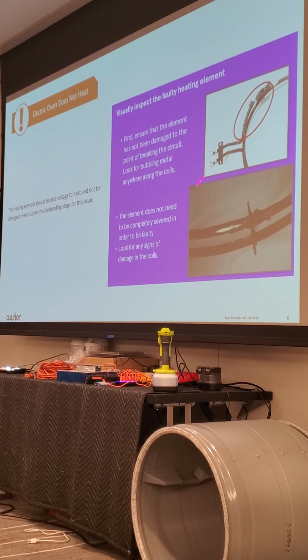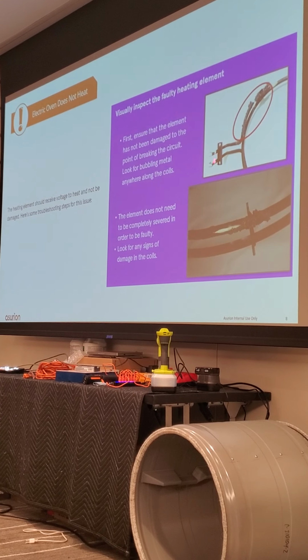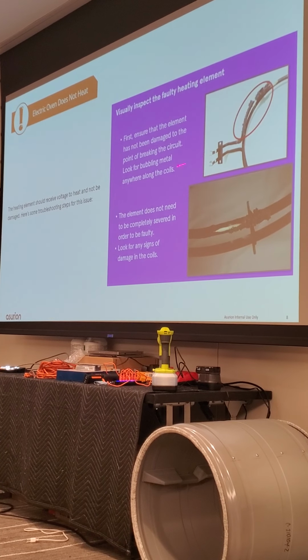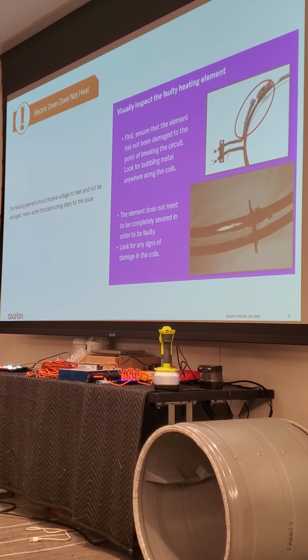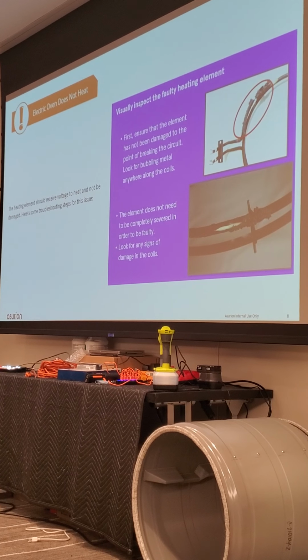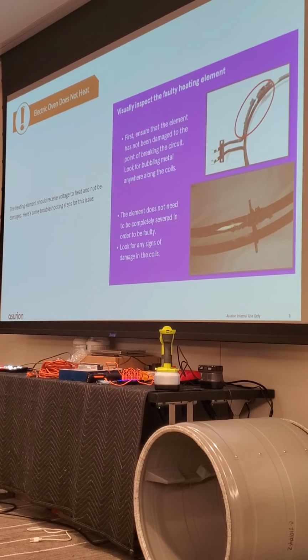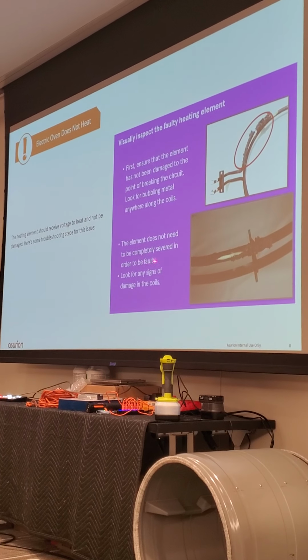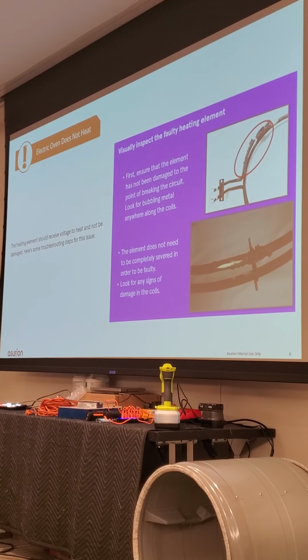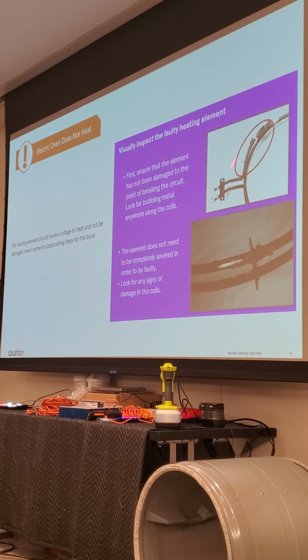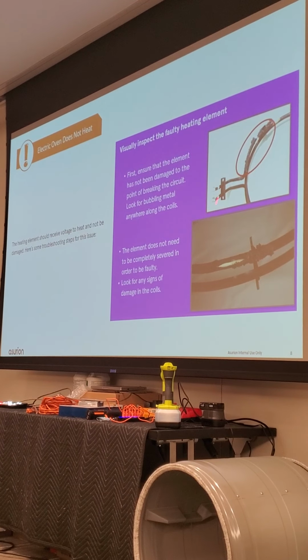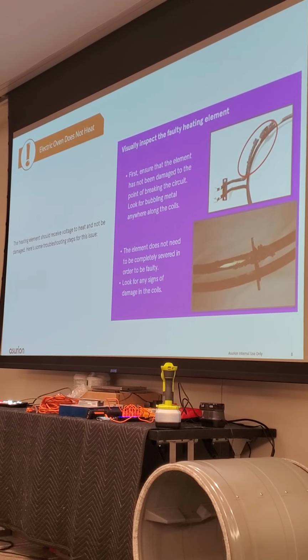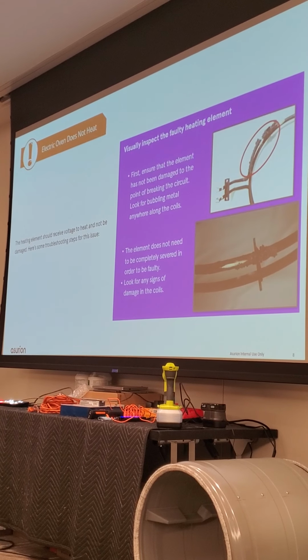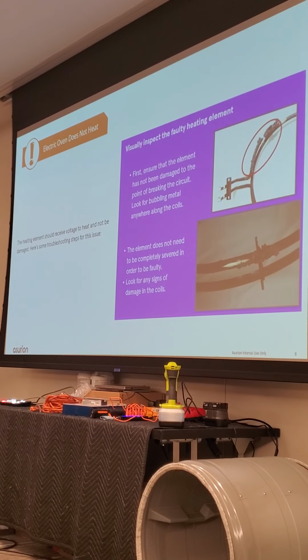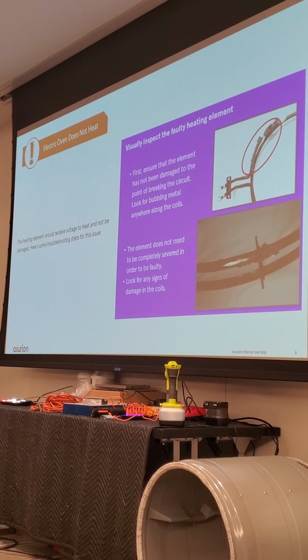You can ohm these out. You can also test the power to them. You might also check the wires out here on the end where they might have melted and burned into. So just make sure you're following standard troubleshooting when you're doing these. You can test the power and the ohms from the board, but then go to the heating element, look at it, test it here, make sure you've got good wires and everything, good connections on that - because I have seen the terminals on these burning too.